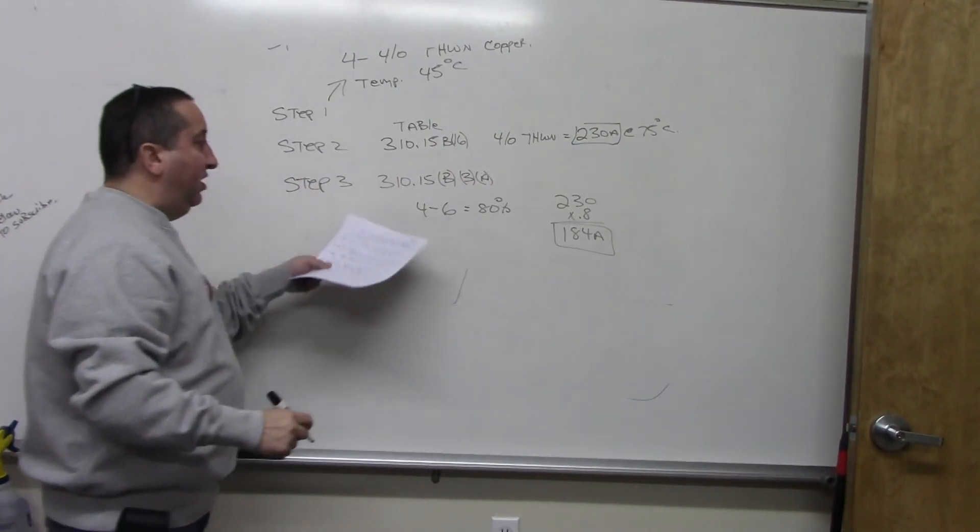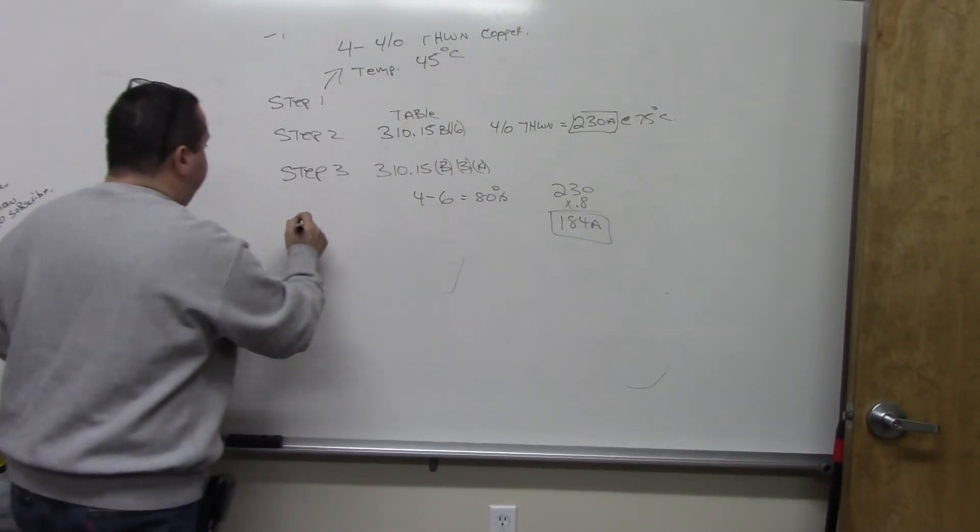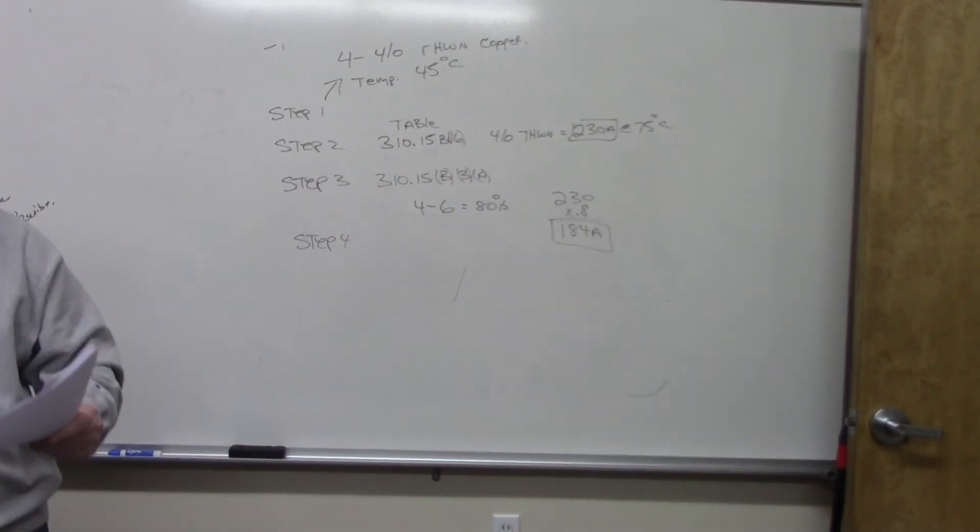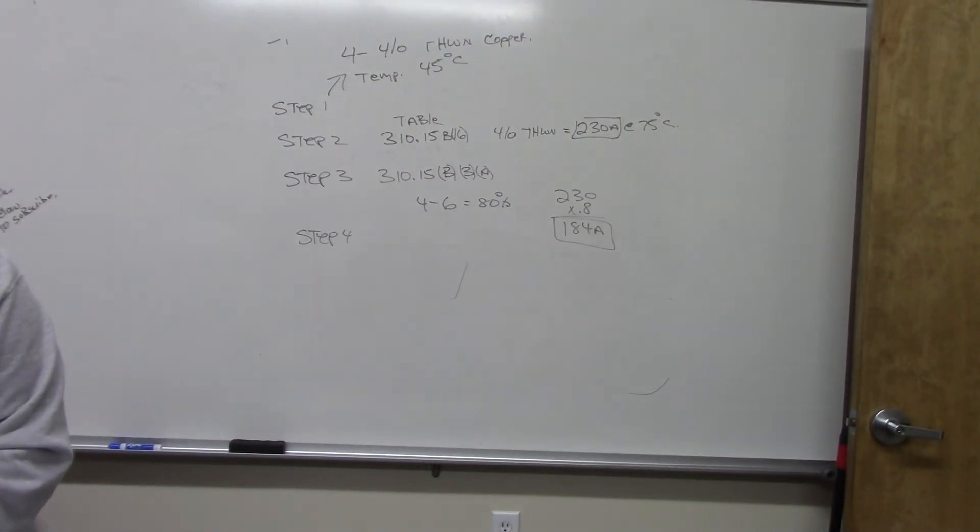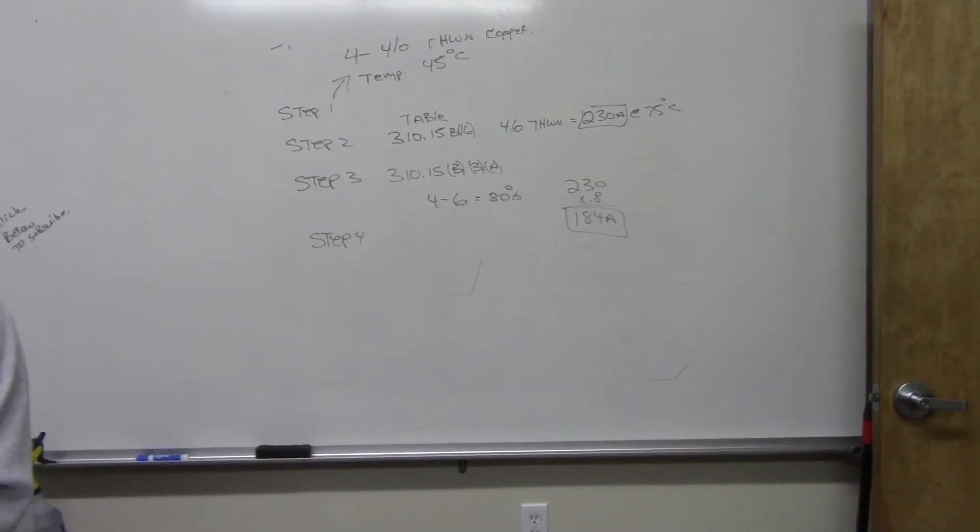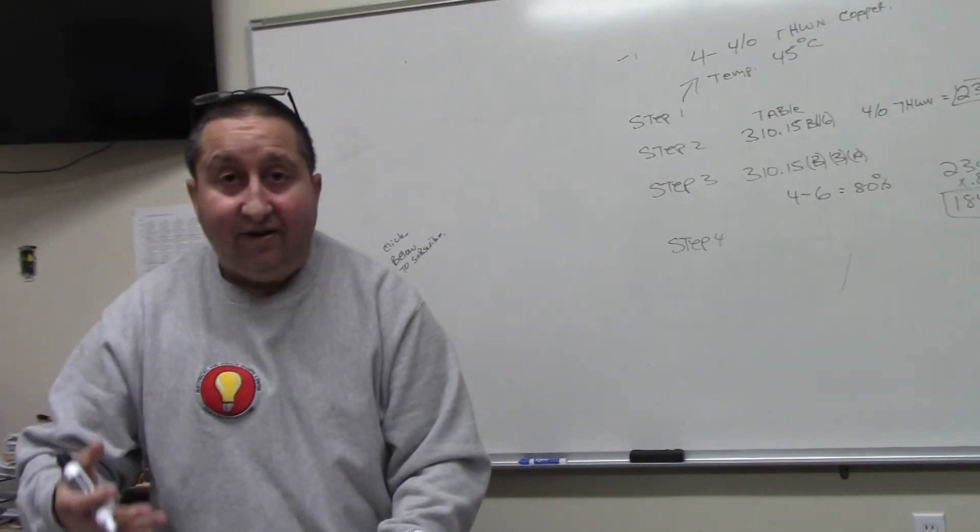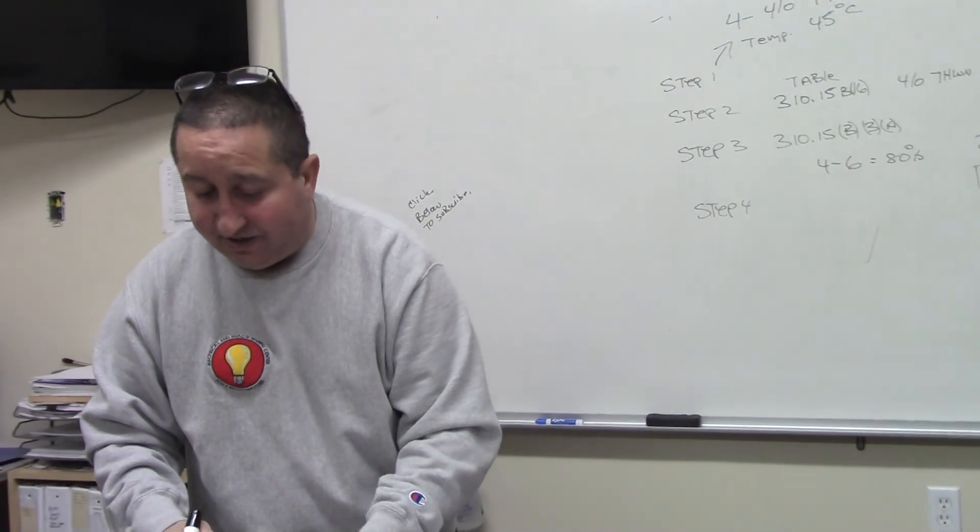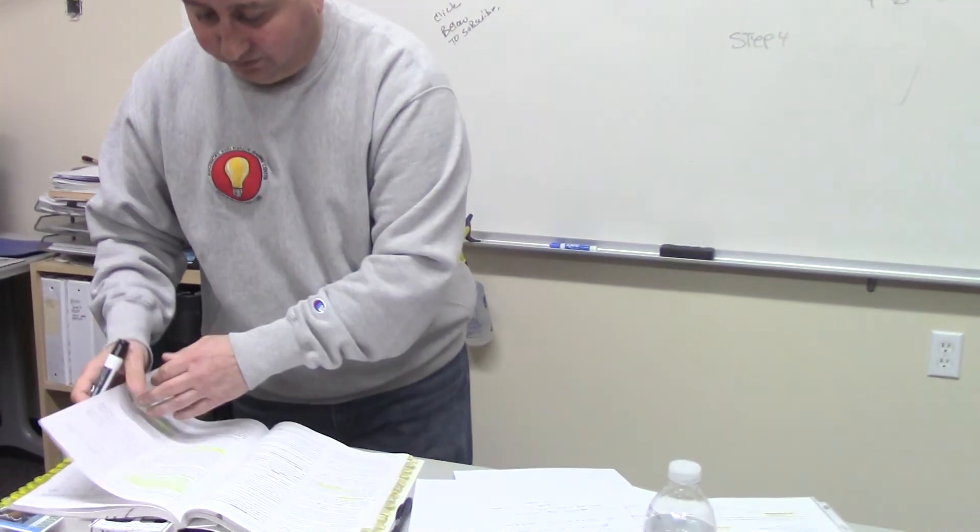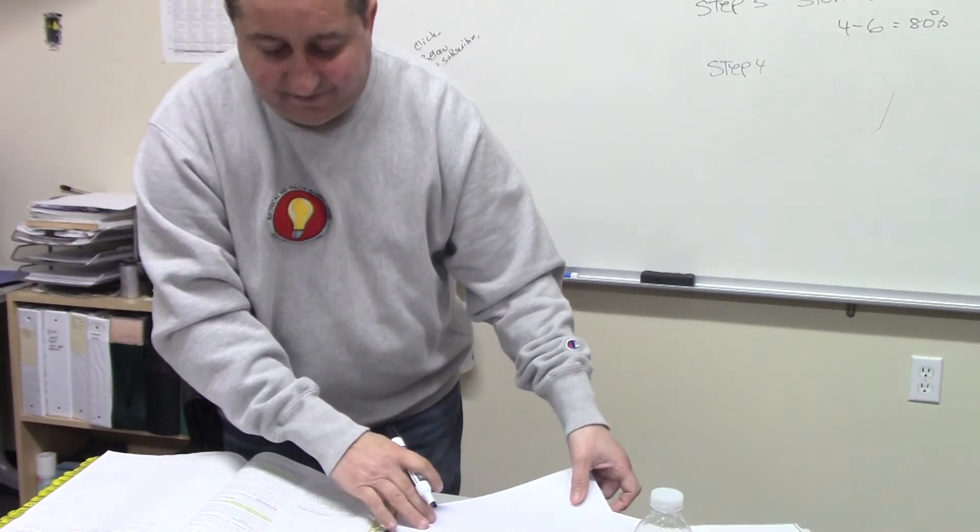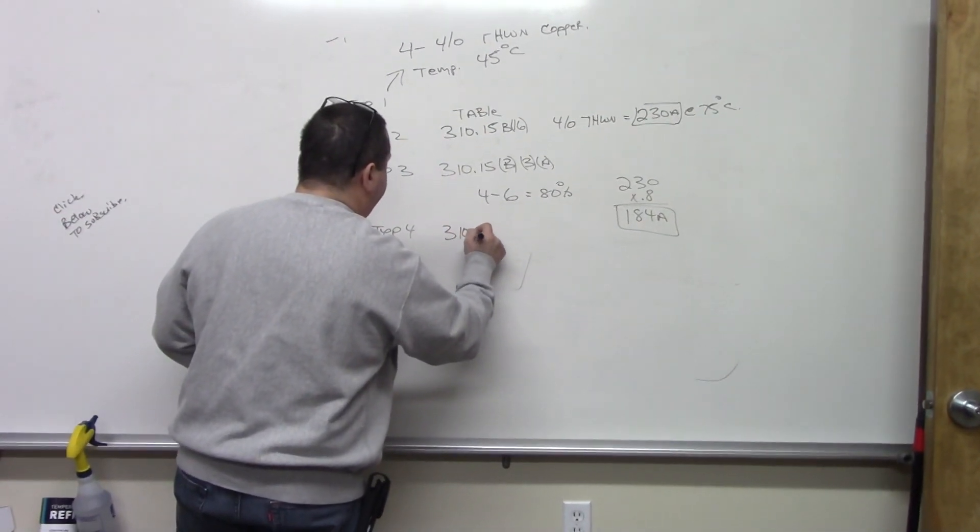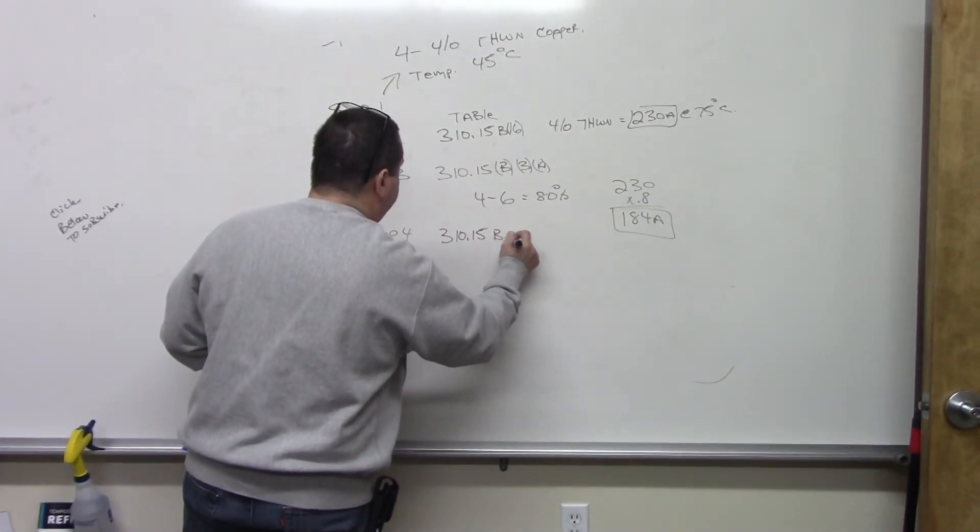That's for the current carrying conductors. Then in step four, we're going to go into the code book. Table 310... and you know what the problem is, every code cycle, they keep changing it on me. So here, it's Table 310.15B2A. We're going to go to 310.15B2A.